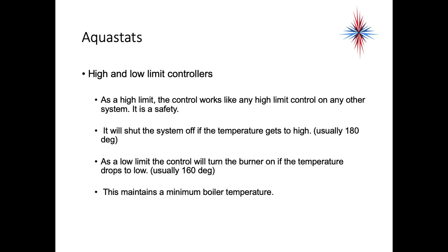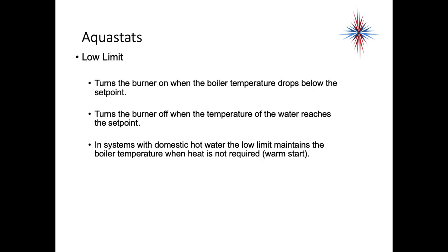As a low limit control, it will turn the burner on if the temperature drops too low, usually about 160 degrees. This maintains a minimum boiler temperature. The low limit control on the aquastat turns the burner on when the boiler temperature drops below the setpoint and turns the burner off when the water reaches the setpoint. In systems with domestic hot water, the low limit maintains boiler temperature when heat is not required — known as a warm start boiler.